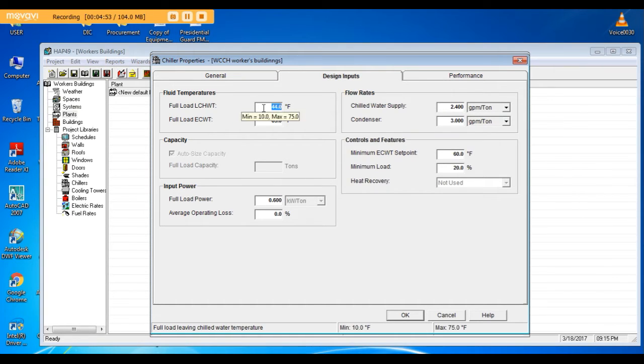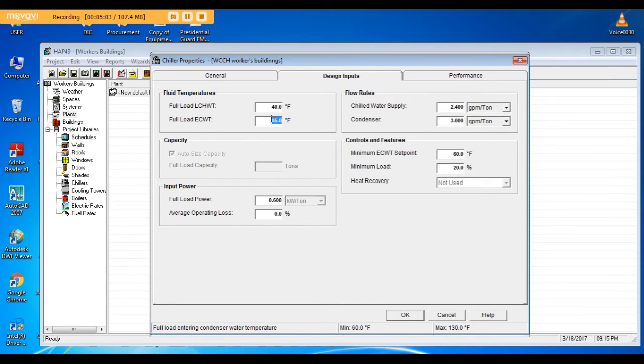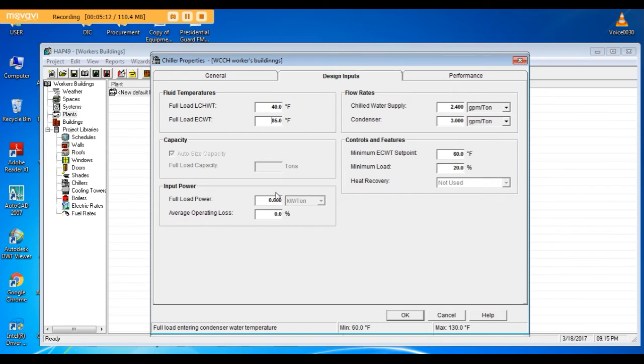The full load leaving chilled water temperature, as we said, 40 degrees Fahrenheit. The entering condenser water temperature I will keep 85 degrees Fahrenheit. Full load power, the efficiency of the chiller: 0.6 kilowatt per ton. You can change it if you have different data.